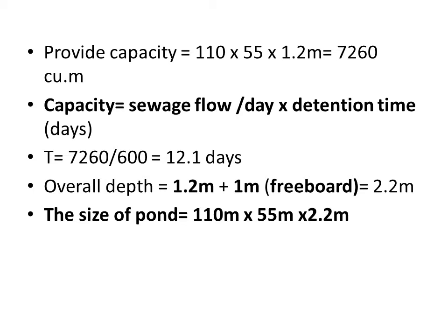Detention time t equals 7260 divided by 600. You will be getting 12.1 days. That is the detention time we have to provide for the oxidation pond.